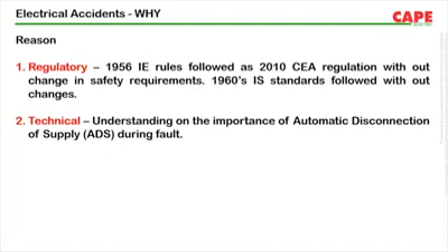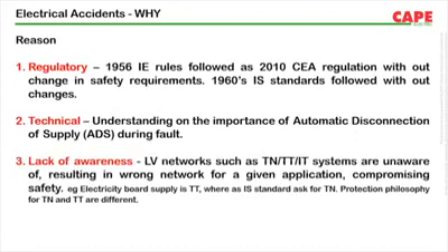The third reason is lack of awareness. Low voltage networks such as TNC, TNS, TNCS, TT or IT are not understood well, resulting in a wrong network for a given application, compromising safety. An example is KSEB supply is TT, whereas the Indian standard or the IE rule or the CEA regulation asks for TNCS system with PME for public low voltage electricity distribution. For example, earthed neutral conductor or earthed neutral terminal explained in CEA regulation is applicable for TN network, not for TT.